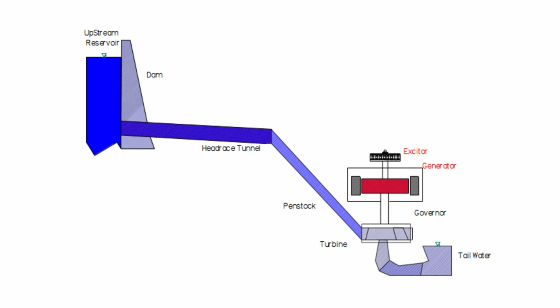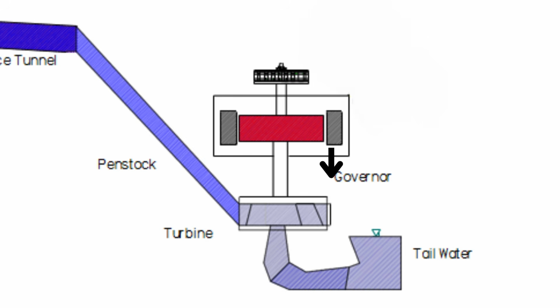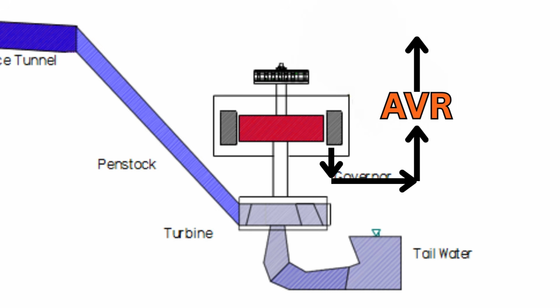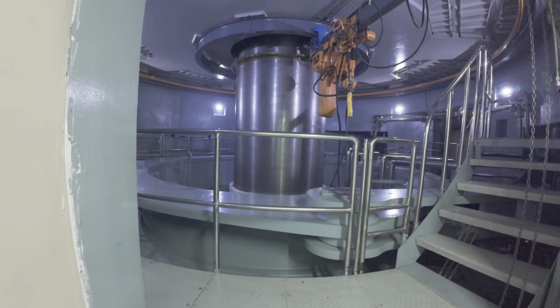Now, here is the engineering dilemma. The system normally gets its power from the generator itself. But during startup, the generator isn't producing electricity yet. So, how do you power the excitation system before the generator can generate power? This is where one of the smartest setup sequences in power engineering begins.